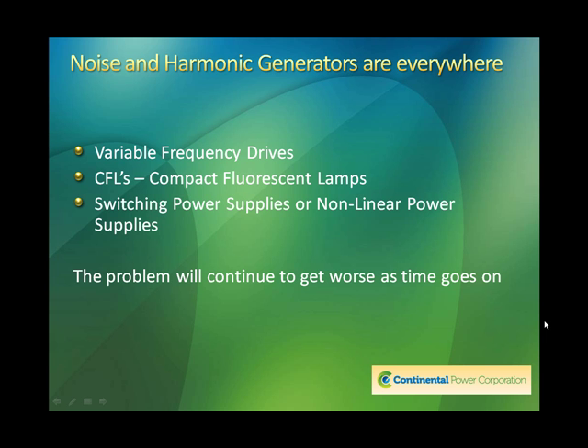In every way they are much better than linear power supplies, which use a typical transformer and a few discrete components. But the problem is that it does generate noise on the line because the power is being used in a very non-linear way. It's either on or off, using an SCR or a triac, and consequently that generates lots of noise. And as I state here, the problem will continue to get worse as time goes on. More and more switching power supplies are being used. Virtually every single device plugged in today has some kind of electronic controller which uses switching power supplies. So this will get worse.